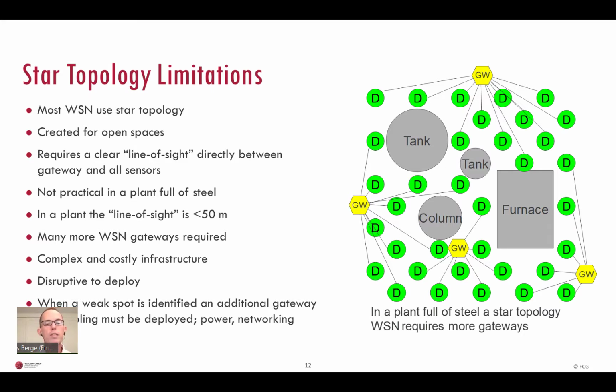So you can't see the gateway from the location of most sensors due to all of the metal obstructions. And therefore, radio waves also cannot reliably reach the sensor. Thus, star topology is not suitable for a plant full of steel. Installing the sensors where there are no structures or far above the ground is not practical. So due to these limitations, many more gateways are required, which would be very costly and disruptive to deploy in an existing plant. So be careful.